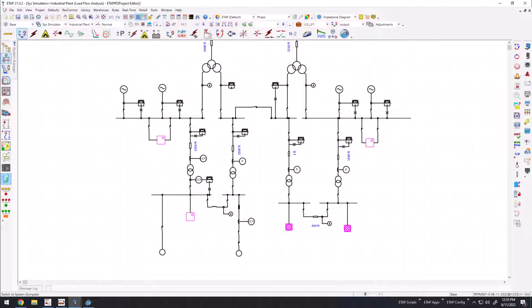Let's take the case of a site that needs to bring down a critical equipment. Before the action is taken, we can simulate opening the circuit breaker and the effects on the system. Now, on the next demo, I will have side-by-side views of the ETAP real-time data showing on the left and also my simulation view showing on the right side. This will help us to take a better look at the simulation result. Here I can make the change and evaluate what will happen. After I open the circuit breaker, now I can run the simulation. As you can see, after opening the circuit breaker, this will cause one of my transformers to overload. Therefore, I must reduce my load before taking this generator offline.